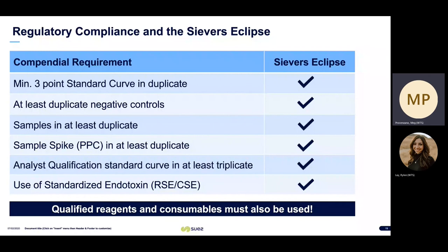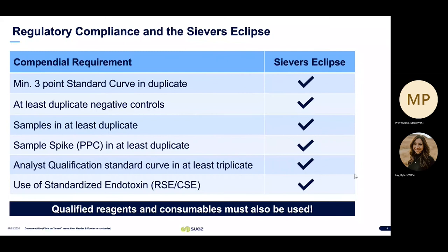How does the Eclipse meet all of these requirements? As mentioned, you can run a minimum three-point standard curve. The standards offered are 50, 5, 0.5, 0.05, and 0.005 EU/mL — not all have to be utilized for each assay, so you could easily run a three-point standard curve if desired. There is a negative control segment so a negative control can be run with each assay. Each sample is run in duplicate along with the sample spike segments, and you can perform analyst qualification easily through the software using a triplicate standard curve.